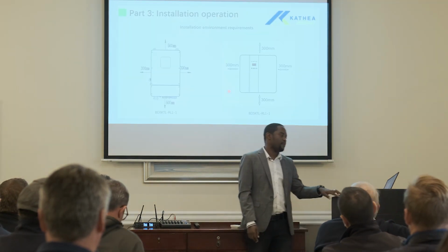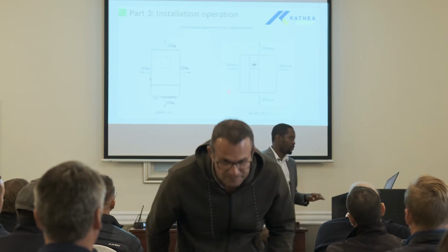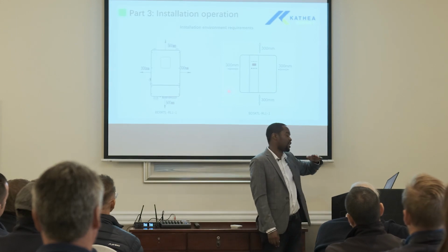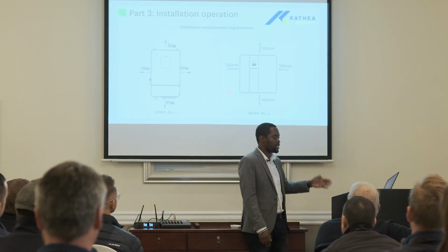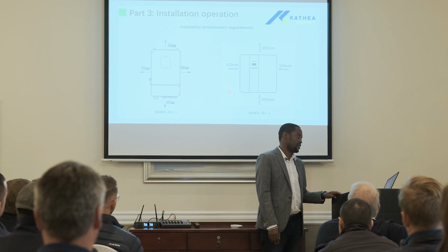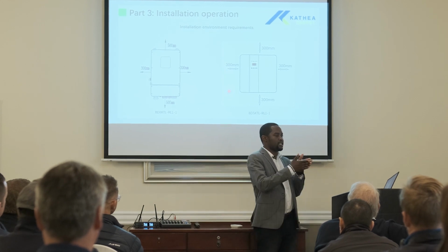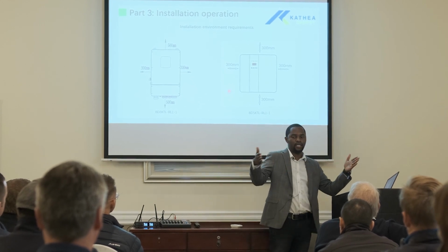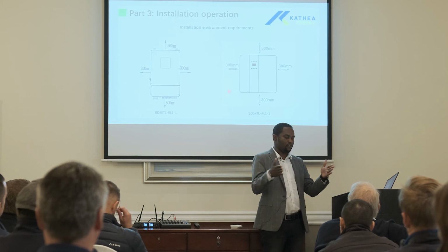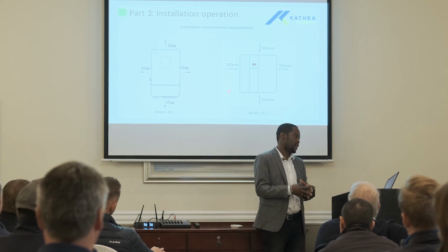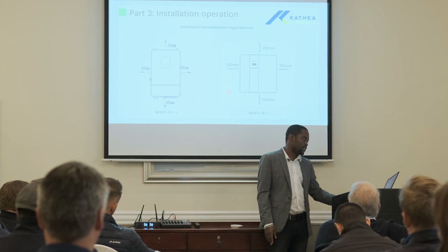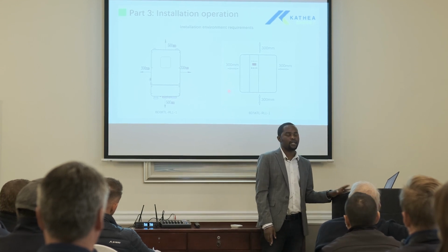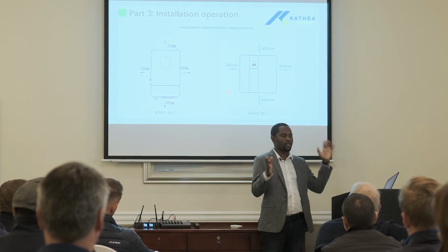If you are installing them, you need to leave at least half a meter from the roof. Then from the walls by the sides, at least 30 centimeters. But now if I've got more in parallel, increase that 30 centimeters from inverter to inverter to at least half a meter again. So you've got half a meter between inverters if they're in parallel. Then for the 5 kilowatt, it's 30 centimeters, 300 millimeters on all the sides.